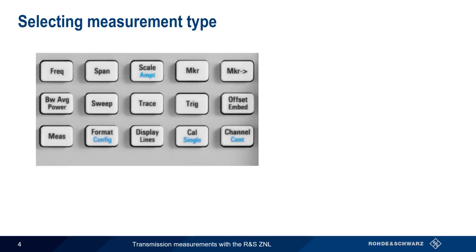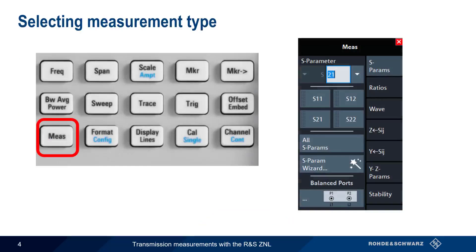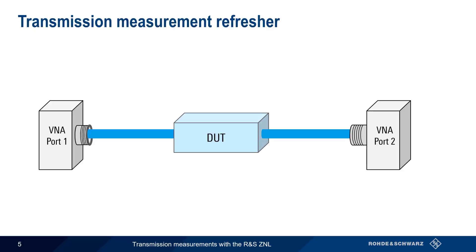To select the measurement type on the ZNL, press the Measure hard key and then choose either S21 or S12 under S-parameters. Remember that in an S21 measurement, the ZNL transmits power on port 1 and measures the power received on port 2, whereas an S12 measurement does the same thing, but in the opposite direction, that is, from port 2 to port 1.